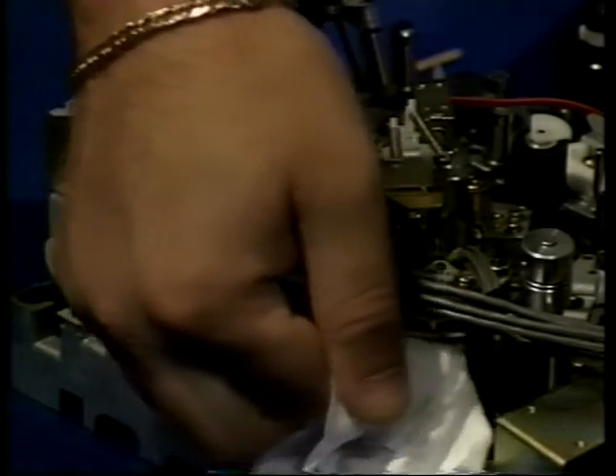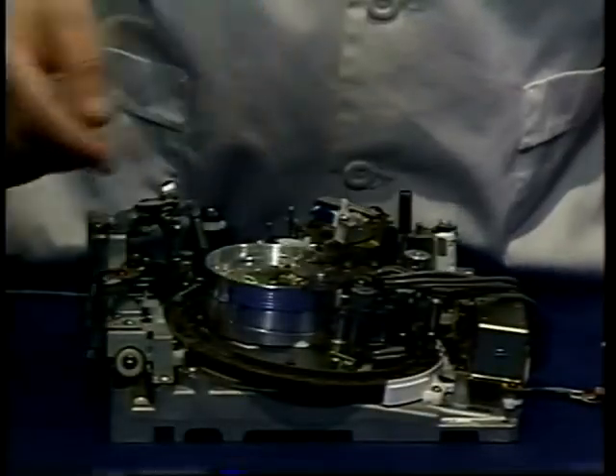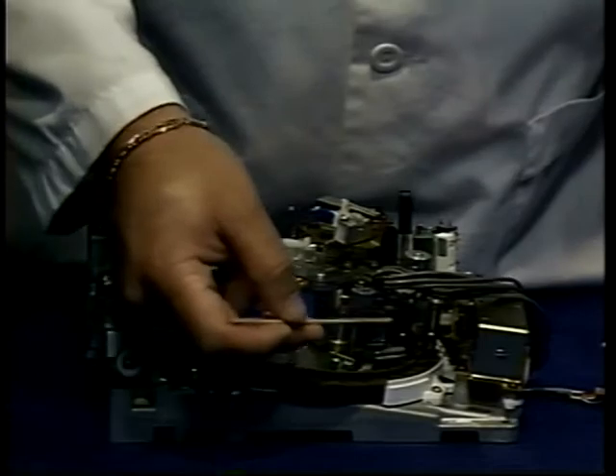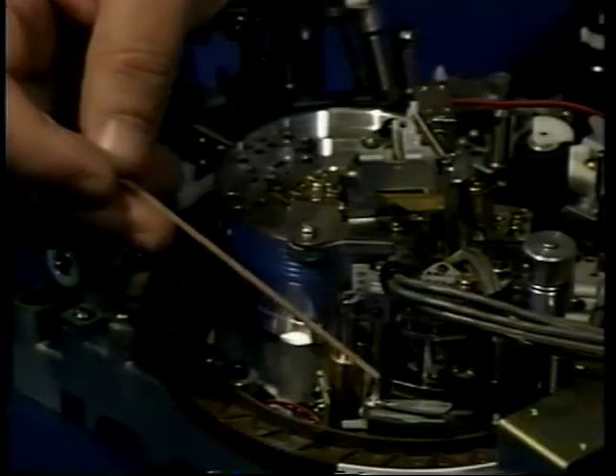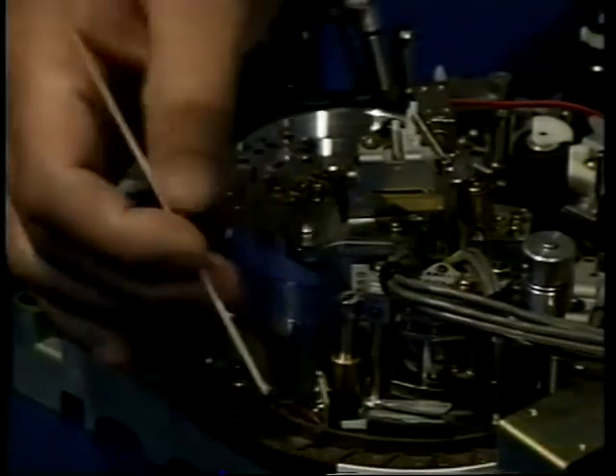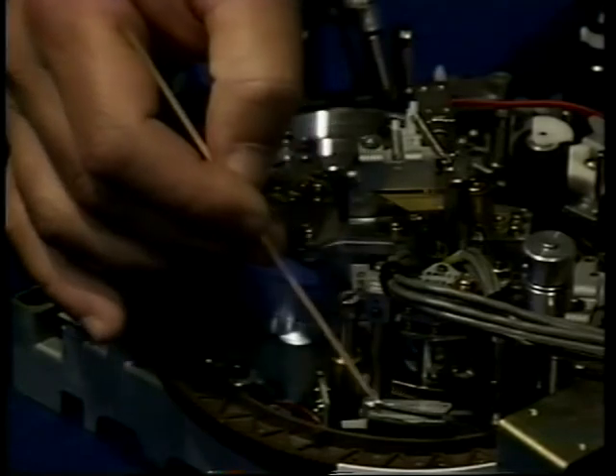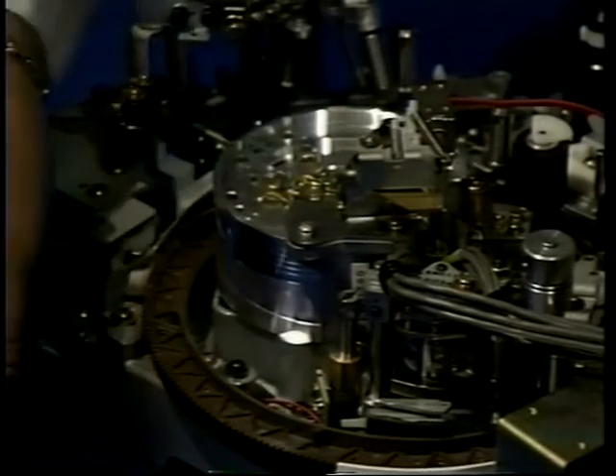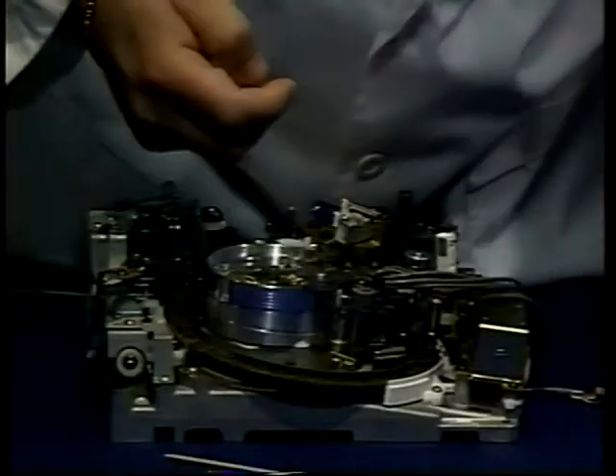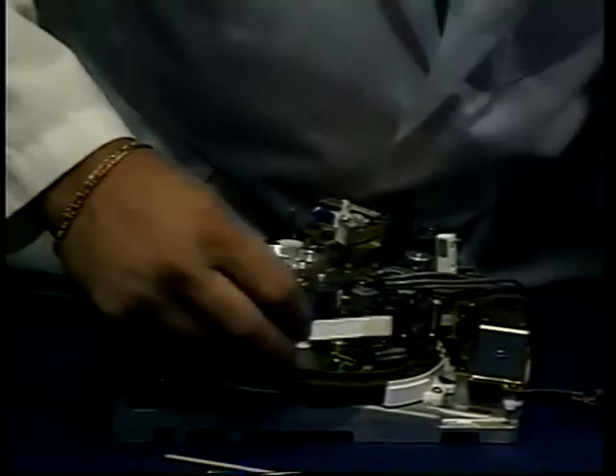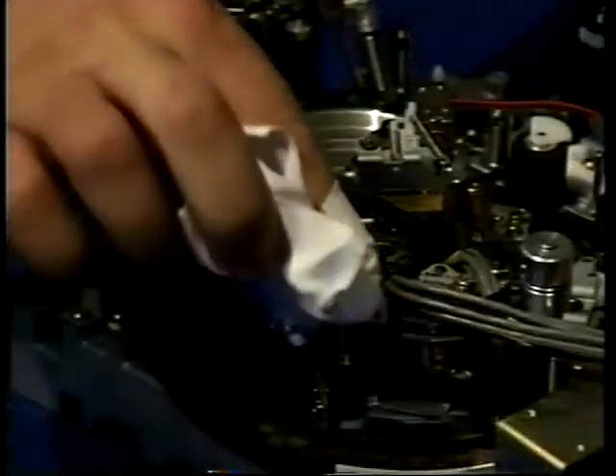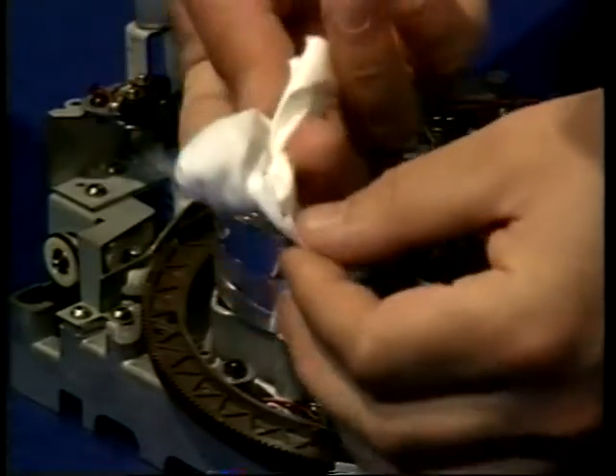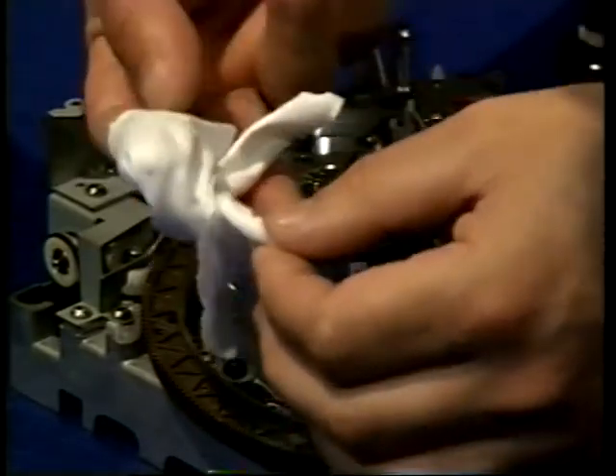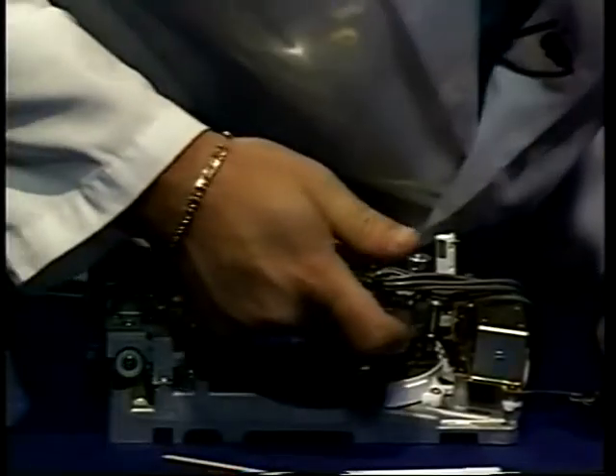Again, remember to use a side-to-side motion. Up and down motion here must be avoided because this would transfer dirt from one head to another. Note that there are moving parts within the chassis that have grease on them, one being this guide right here. Exercise care to avoid transferring this grease. Cleaning sticks are recommended because they don't come into contact with the grease. When using Tex wipes, avoid contacting the grease, and if grease does get on the wipe, discard it to prevent the grease from getting on the head.